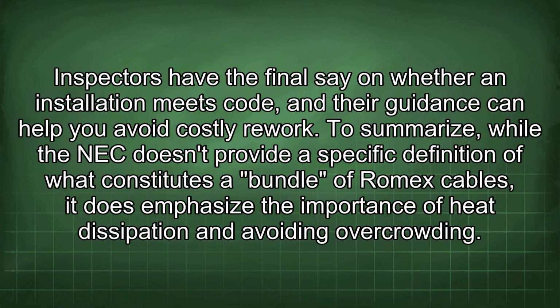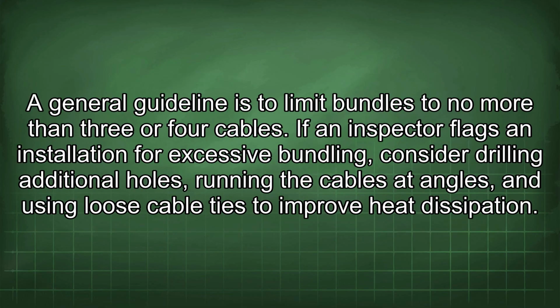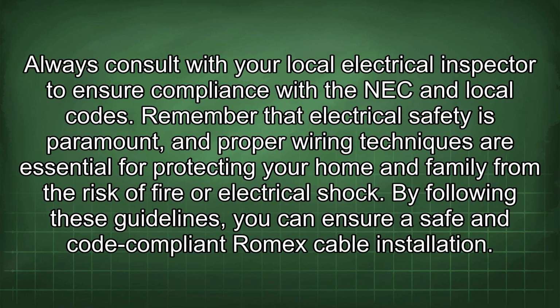cables, it does emphasize the importance of heat dissipation and avoiding overcrowding. A general guideline is to limit bundles to no more than 3 or 4 cables. If an inspector flags an installation for excessive bundling, consider drilling additional holes, running the cables at angles, and using loose cable ties to improve heat dissipation. Always consult with your local electrical inspector to ensure compliance with the NEC and local codes.